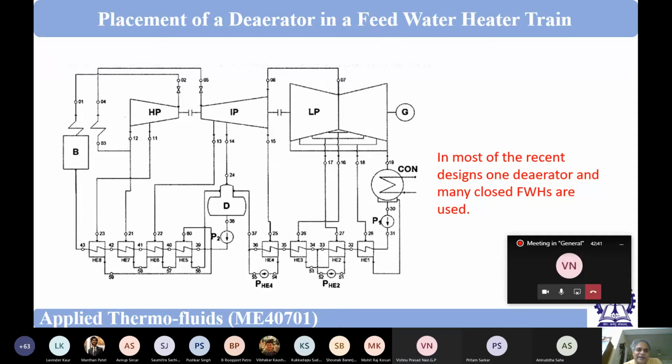The other advantage is that, let us go a little bit into applied mechanics, the turbine shaft is rotating and through the blade passages steam is expanding. So there is a change in pressure, high pressure to low pressure. And obviously, there will be thrust. There will be radial thrust and there will be axial thrust. So for the axial thrust, there will also be some sort of bearings, etc. Radial and axial thrust one has to take care of.